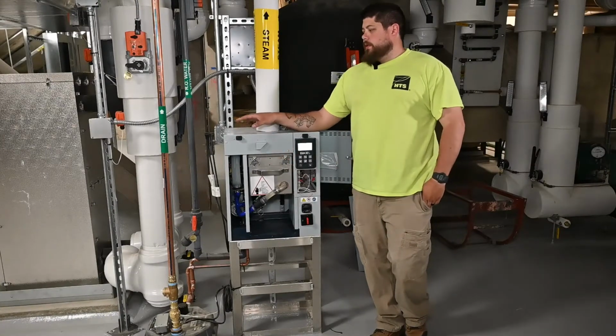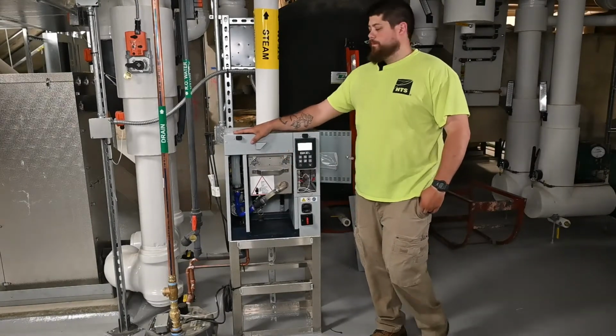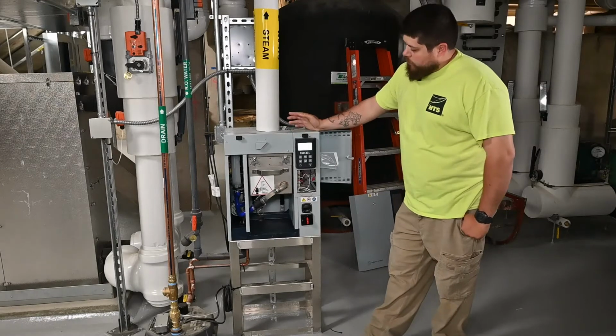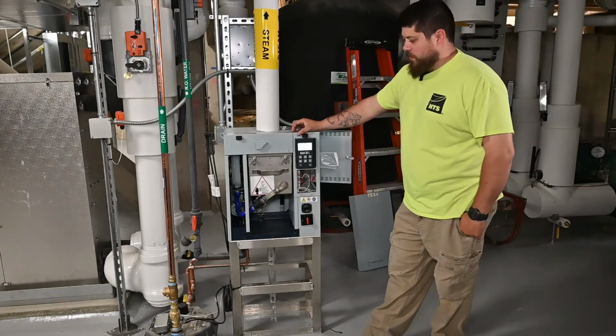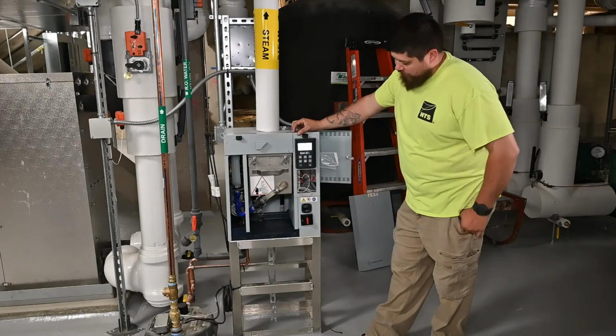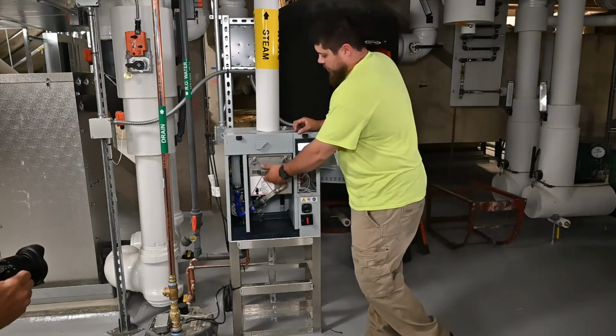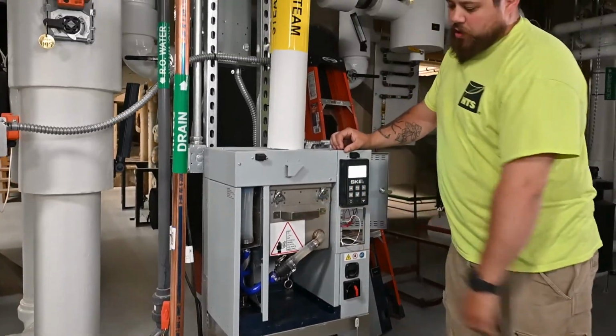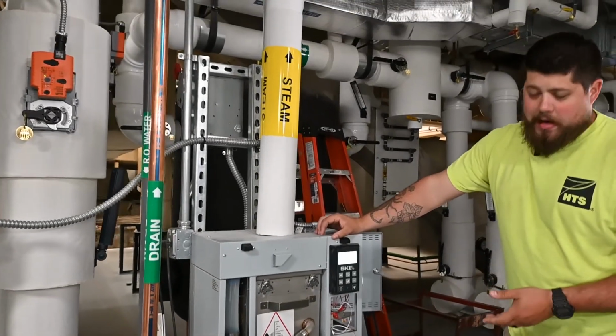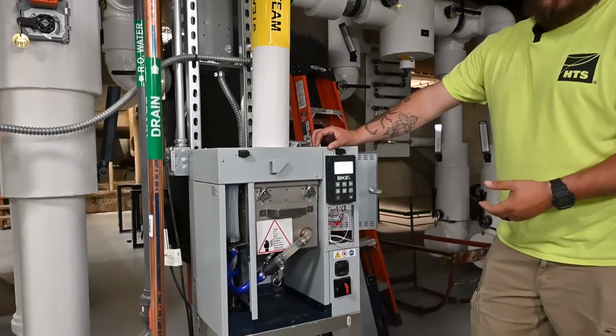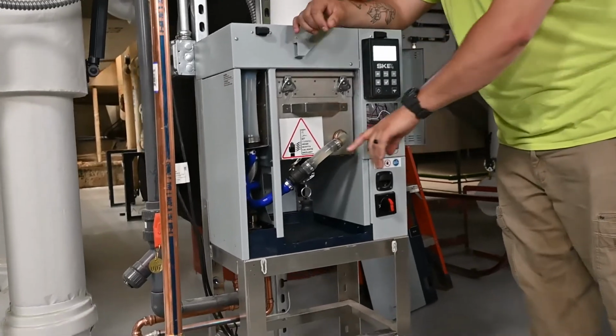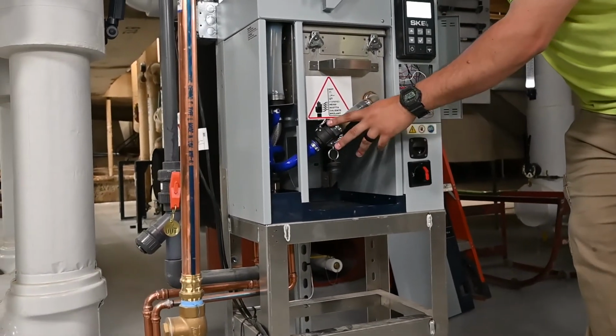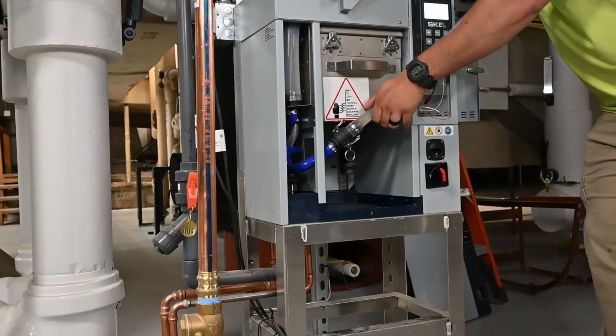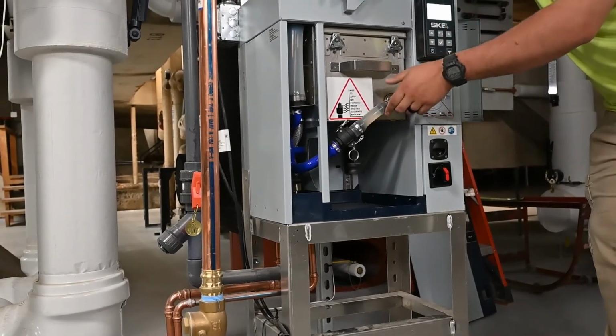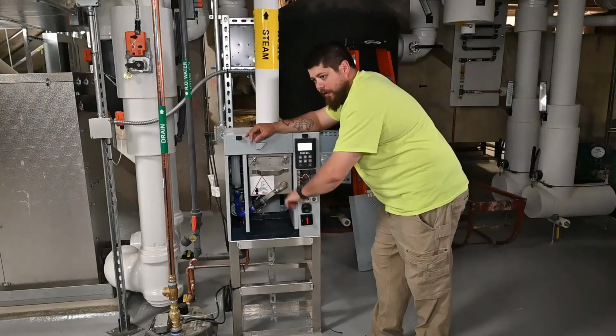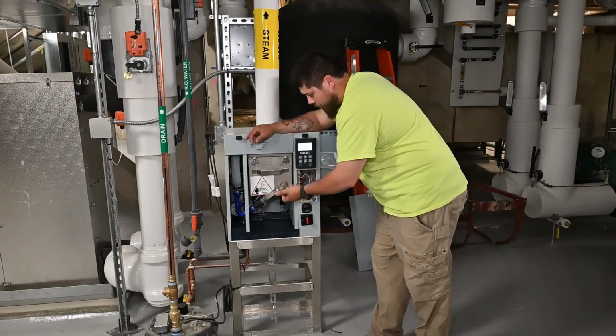So this is an Ebtronic humidifier. They're very small. They're very simplistic as far as the humidifier industry goes. This right here is where you're going to actually be holding your RO water. It's very easy to actually do maintenance on these, which is why I actually enjoy the Ebtronic line as a manufacturer. These two clips here can unbuckle, and you can disconnect this. They use fire hose connections to be able to connect this lining. After that, these can open up and it'll drop down and slide on a rail. You can pull this out.